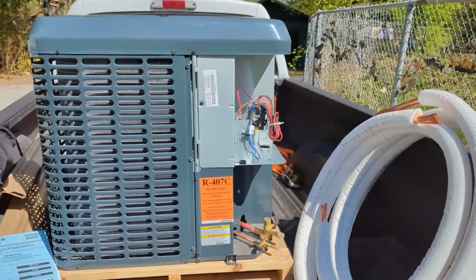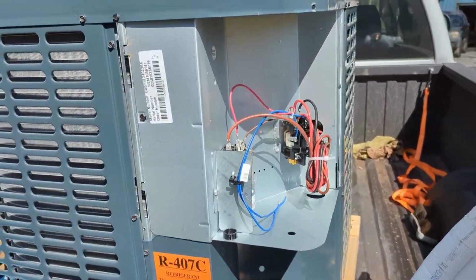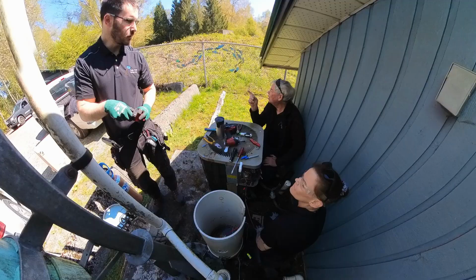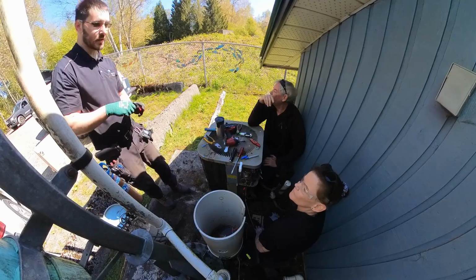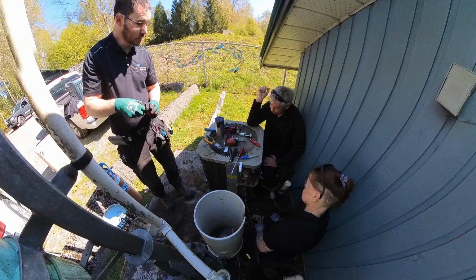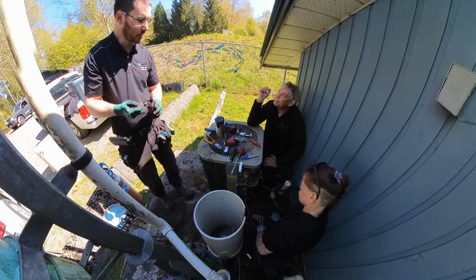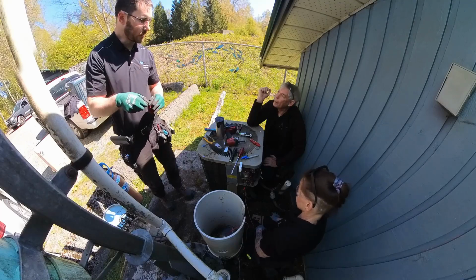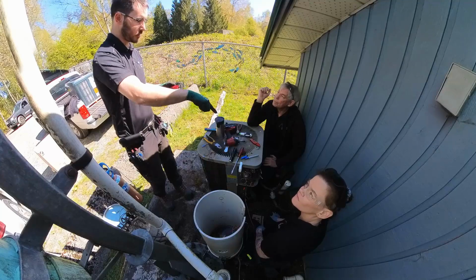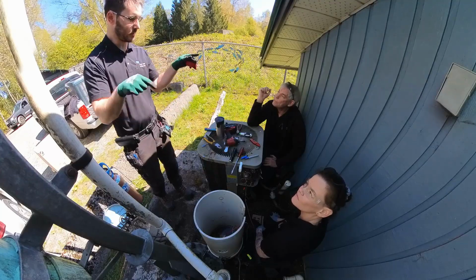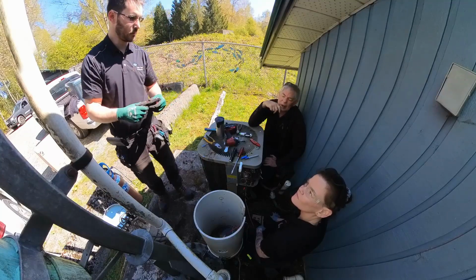Here's our new unit, and as you can see, there's a whole lot less components in there. No, that's cooling only as well. I'm telling Jess the reason why the wiring is different in this is because it's cooling only, not a heat pump. That's why it goes straight from thermostat to contactor. It doesn't go to the bundle, which then splits off and goes to the contactor.